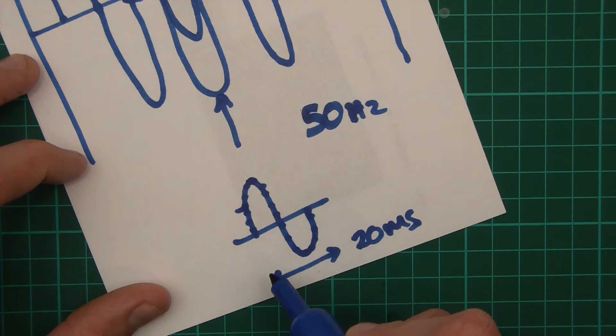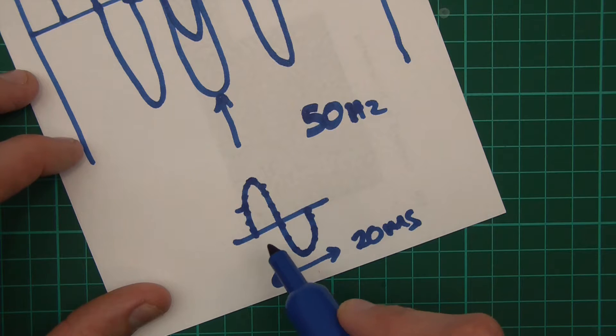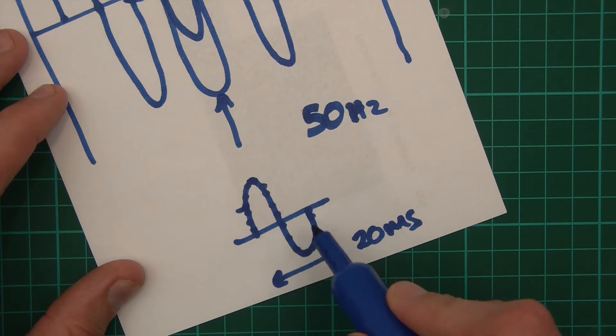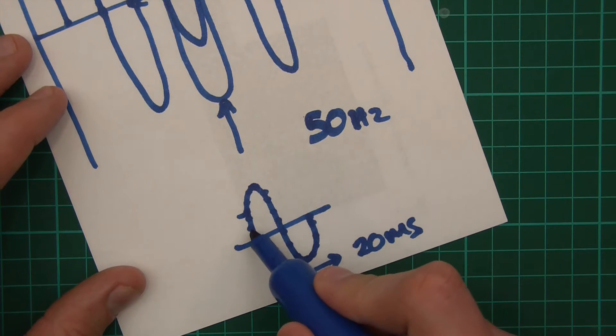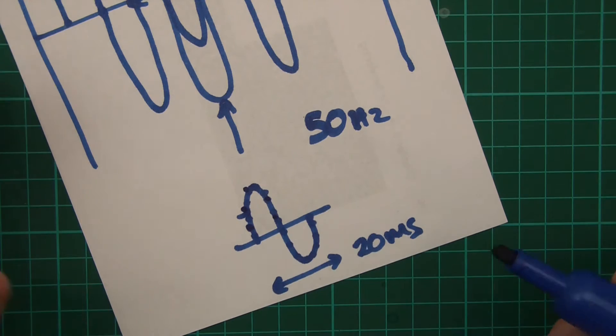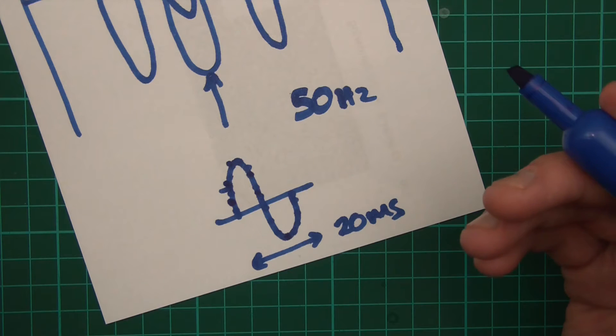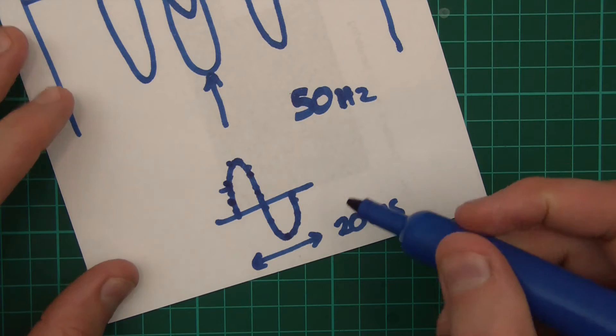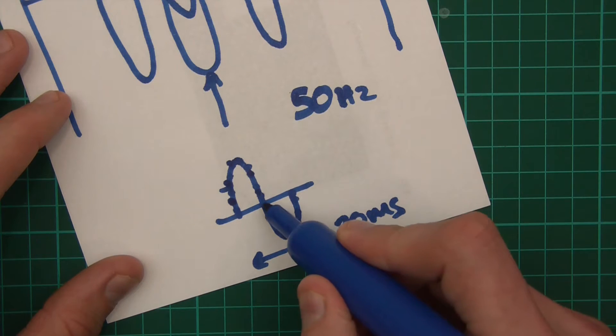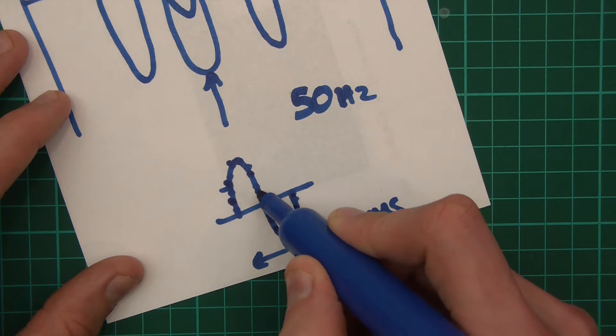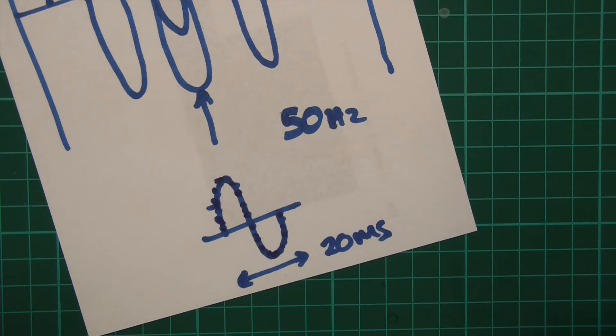So if we were to take 10 samples every 20 milliseconds — one every 2 milliseconds — we'd get about five samples of the positive part of the voltage and five samples of the negative part. Would that be enough? If we miss the peak and the trough, we're not going to get accurate results. So even 10 samples over one wave is not enough. Let's take 20 samples over one wave — 10 samples per half — so 10 samples of the negative and 10 of the positive. And that will now be sufficient.